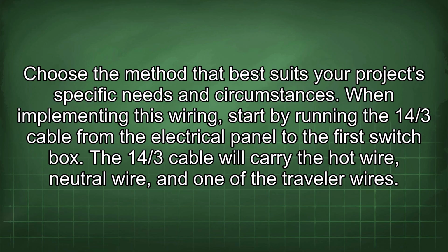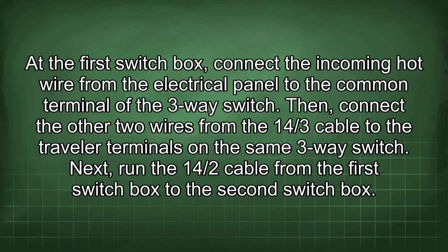When implementing this wiring, start by running the 14/3 cable from the electrical panel to the first switch box. The 14/3 cable will carry the hot wire, neutral wire, and one of the traveler wires. At the first switch box, connect the incoming hot wire from the electrical panel to the common terminal of the three-way switch. Then connect the other two wires from the 14/3 cable to the traveler terminals on the same three-way switch. Next, run the 14/2 cable from the first switch box to the second switch box.